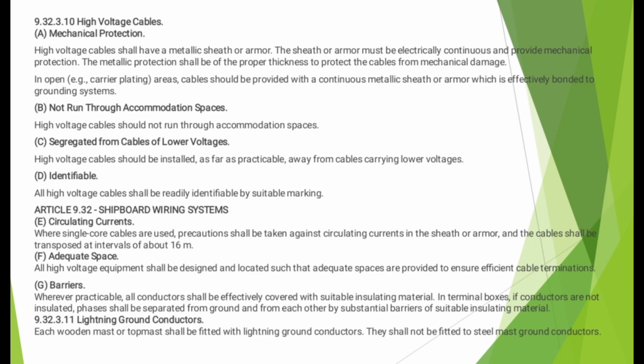In open areas, cables should be provided with a continuous metallic sheath or armor which is effectively bonded to grounding systems. Not run through accommodation spaces. High voltage cable should not run through accommodation spaces. Segregated from cables of lower voltage. High voltage cable should be installed as far as practicable away from the cables carrying lower voltages. Identifiable. All high voltage cables should be readily identifiable by suitable marking.